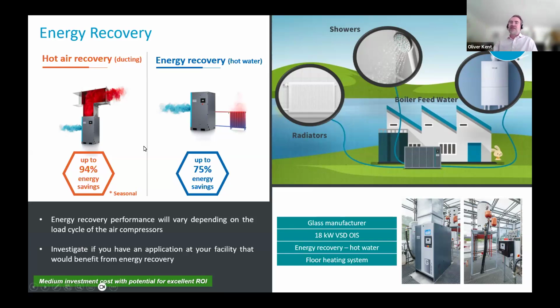The simplest way, if we've got an air-cooled machine, is to take the warm air off our air-cooled machine and divert it into, for example, a warehouse next door. So that warm air is helping heat our warehouse. It's a little bit limited. Firstly, it's seasonal. In the summer, you won't be getting the benefits of your energy recovery. Secondly, it's very low-grade heat, so you can't transport that heat very far. Ideally, you want the user of that heat to be right next to where you're generating your compressed air. So it's very restrictive, very limited in its application.